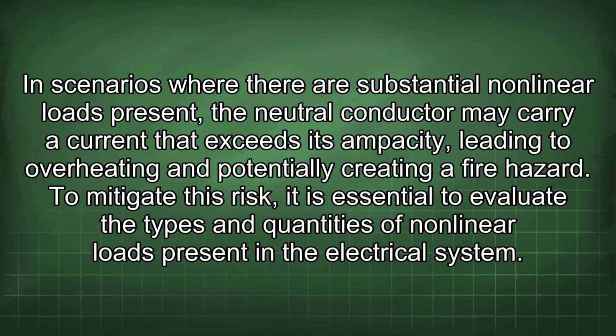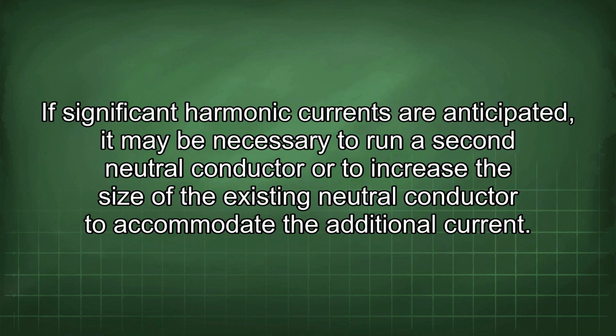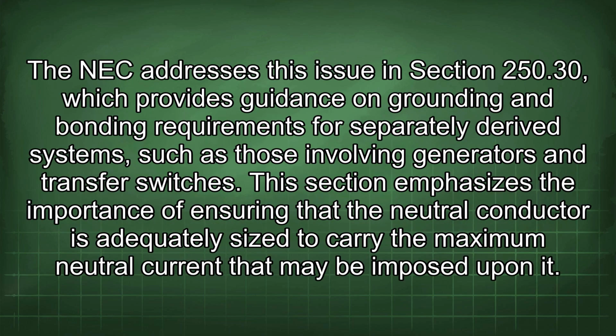To mitigate this risk, it is essential to evaluate the types and quantities of nonlinear loads present in the electrical system. If significant harmonic currents are anticipated, it may be necessary to run a second neutral conductor or to increase the size of the existing neutral conductor to accommodate the additional current. The NEC addresses this issue in section 250.30, which provides guidance on grounding and bonding requirements for separately derived systems such as those involving generators and transfer switches. This section emphasizes the importance of ensuring that the neutral conductor is adequately sized to carry the maximum neutral current that may be imposed upon it.